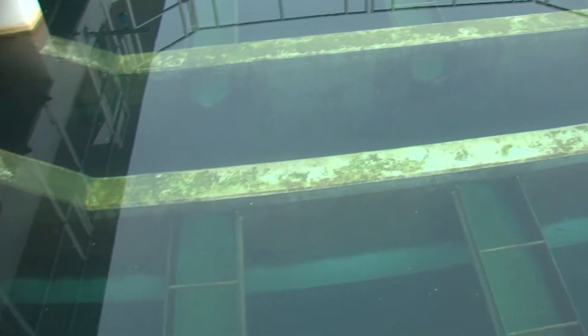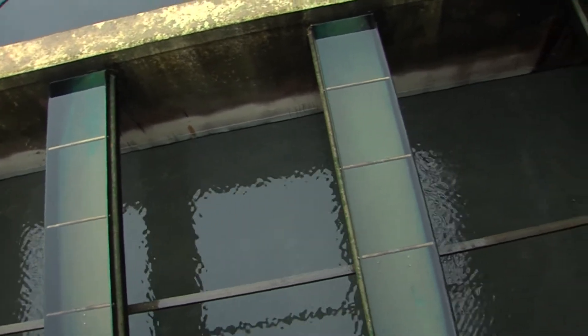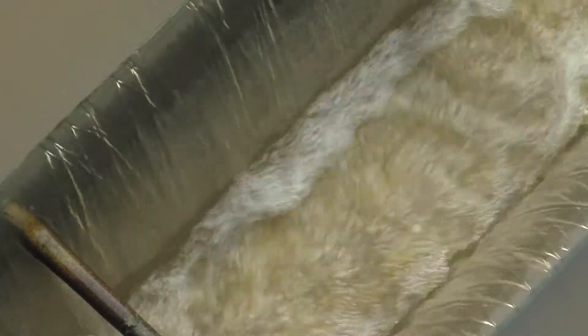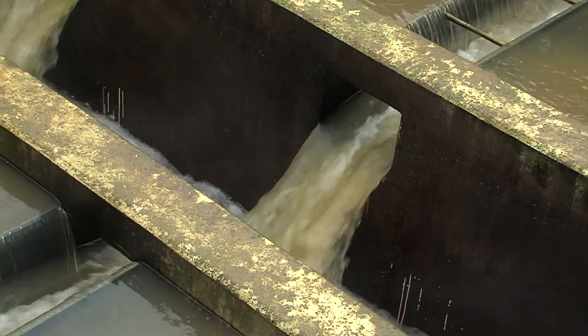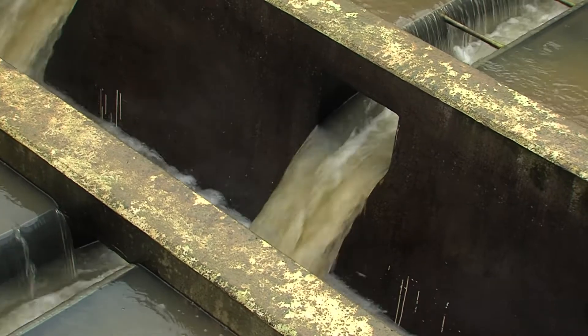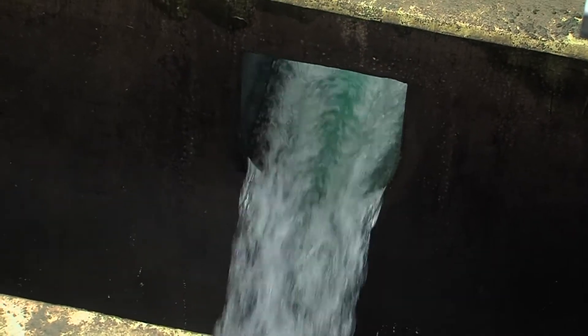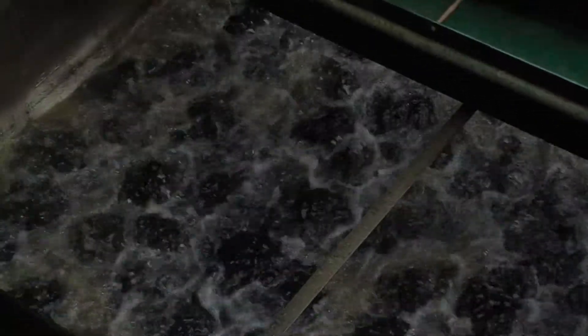Now let's visit the filters. This is the final process that the water goes through before it's complete. This is a filter wash — it's fixing to start. You can actually see the anthracite coal on the bottom here. After the filter runs its allotted number of hours, we take it out of service and backwash it to remove the dirt, and then once it's clean we can put it back in service. There are small fine particles left at the end of the sedimentation basin, and the filters actually take those leftover particles out of the water so that when the water comes from this process, it's as clean as it comes to your sink. The bubbles are starting to come up — as that air comes up through the filter, it literally causes a scrubbing action for the coal.